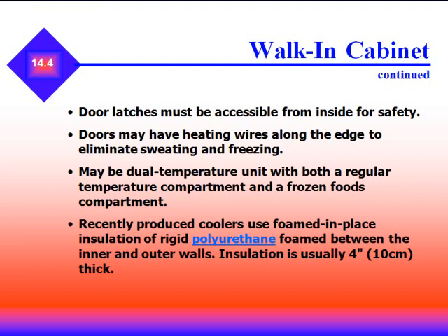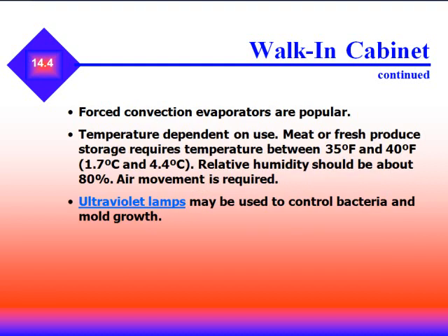The box may be a dual temperature unit with both a regular temperature compartment and a frozen foods compartment. Recently produced coolers use foam-in-place insulation of rigid polyurethane foam between the inner and outer walls, usually 4 inches thick. They have forced convection evaporators — fan-blown evaporators are very popular. Temperature is dependent on use; meat or fresh produce storage requires temperatures between 35 and 40°F, with relative humidity of about 80%. Constant air movement is required.